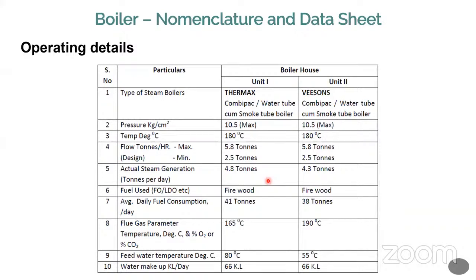Okay. Now the feed water temperature is 80 degrees and 55 degrees. I will tell you what the feed water temperature is. The makeup water in terms of kiloliter per day is 66 kiloliters, or 66,000 liters, for both cases. Okay, these are all the basic parameters represented in the boiler. Of course, not all the parameters are represented on the boiler. Not all the parameters are directly connected to the boiler. Some parameters are directly connected, like tonnage, average steam production, pressure, the name of the company. These are directly connected to the boiler, but the others are connected to the auxiliaries of the system.